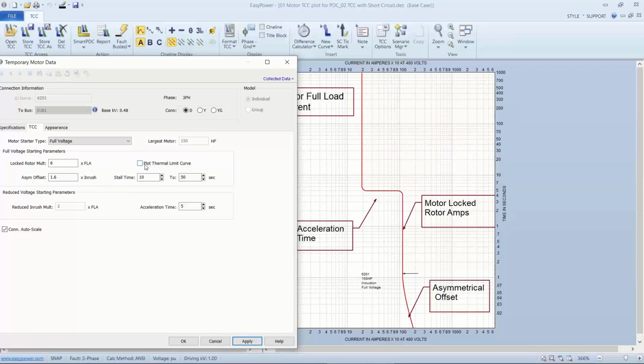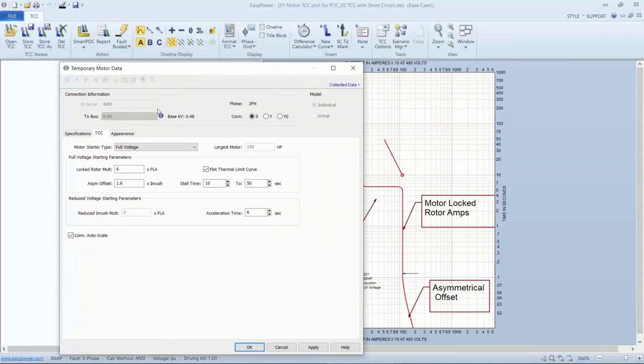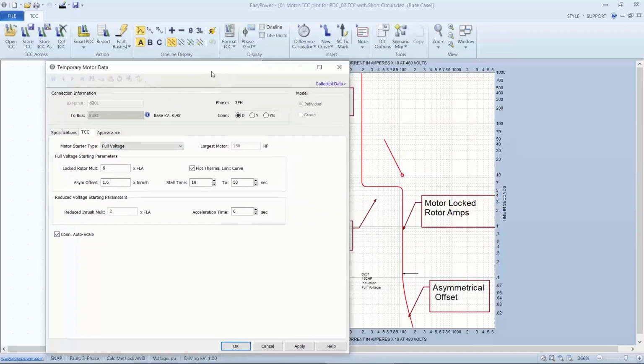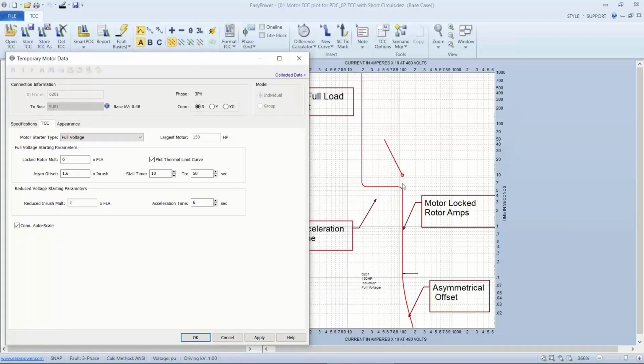There is a limit that we want to make sure we never exceed, and that's called the thermal limit curve. Once we check this box, then we can show the stall time by this short stubby plot. And as we're setting our protective devices, we want to make sure we don't allow the current and time to reach a point up to or to the right of this particular plot. Okay, so then the task becomes making sure we have properly characterized the motor itself when we set it up, and then we're given the target range for operation and protection on the TCC curves.